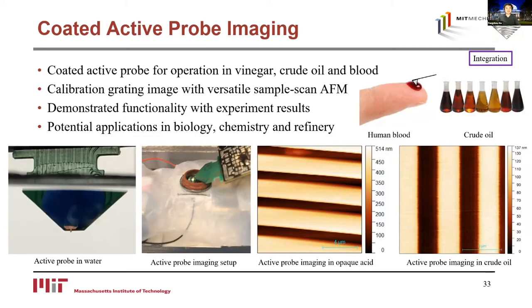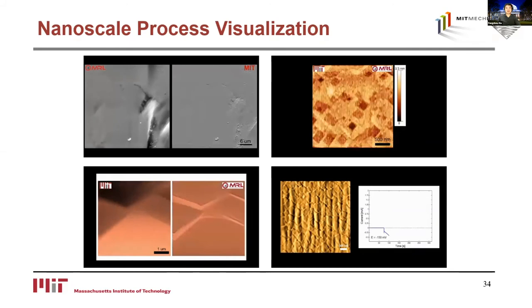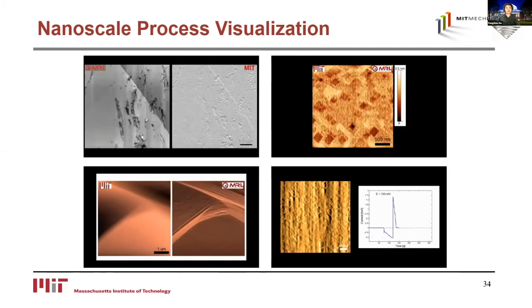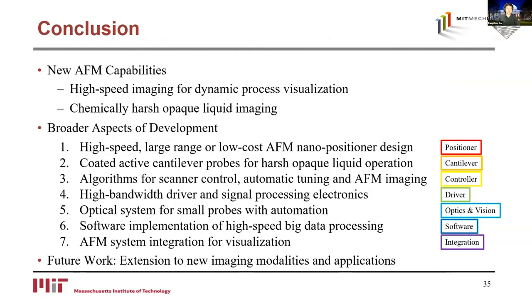Here is a summary of chemical reaction processes that have been visualized in the Mechatronics Research Lab using the high-speed AFM developed in our group, including selected examples of etching and electrochemical deposition. To summarize, this work enables high-speed imaging for dynamic process visualization and chemically harsh opaque liquid imaging. A low-cost educational AFM design is also discussed as an additional benefit. The new capabilities are demonstrated with imaging results, and the development of a custom AFM system is a comprehensive process broadly involving positioner, cantilever, controller, driver, optics and vision, software, and overall system integration. The development contributes to both the AFM user community and the precision instrumentation and mechatronics communities.